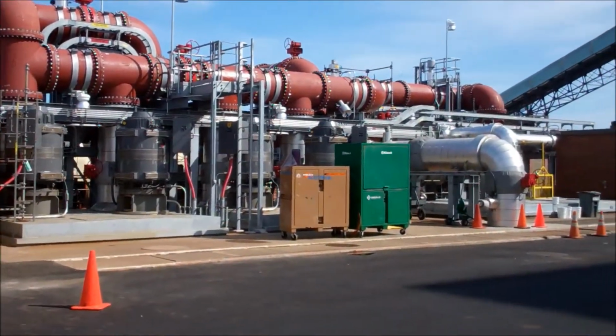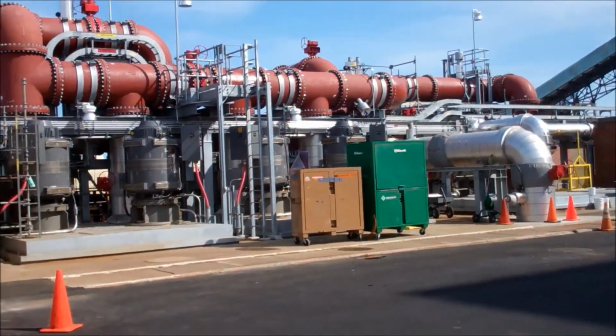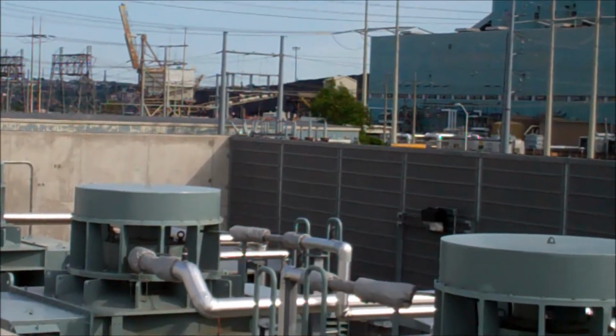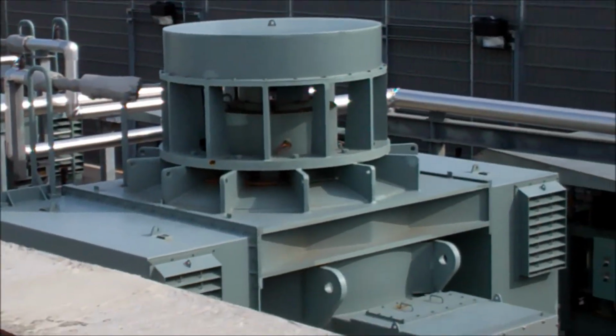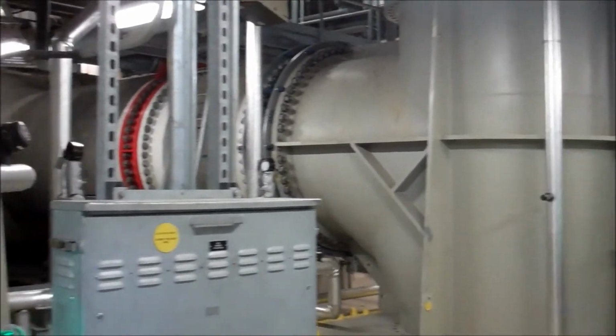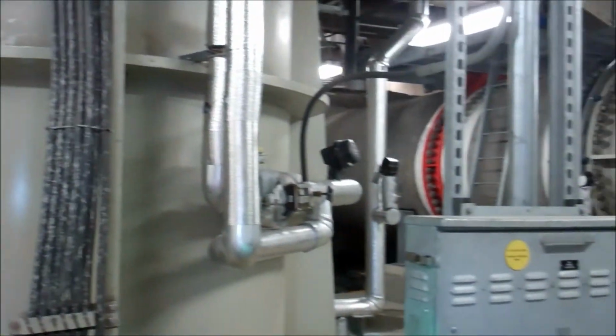This water is pumped through an array of pipes and filtered through screens that filter out any fish or aquatic organisms. This filtered ocean water is then pumped into the plant where it acts like a radiator. Once used, the warm water is then pumped out to the cooling towers using high-volume pumps. The pump station was built in conjunction with the cooling towers and is the home of hundreds of feet of conduit and walls of electrical components.